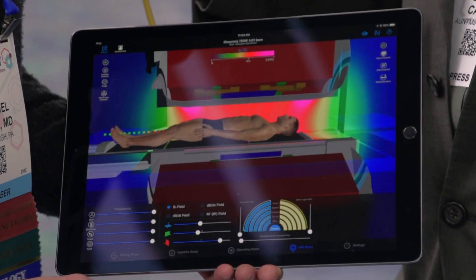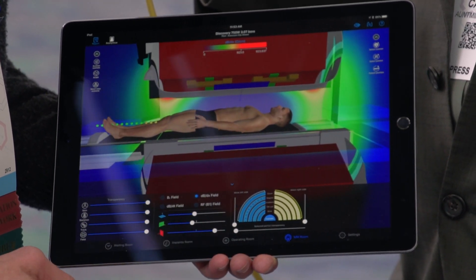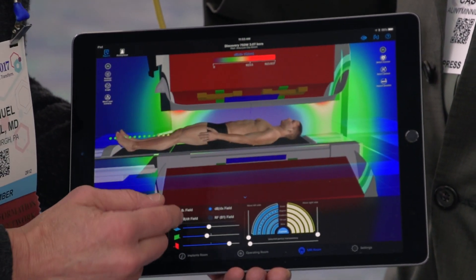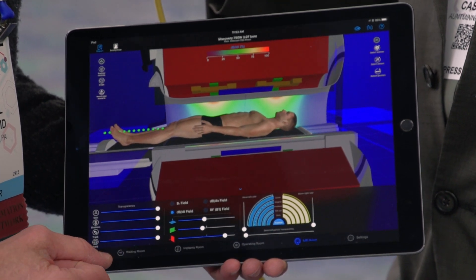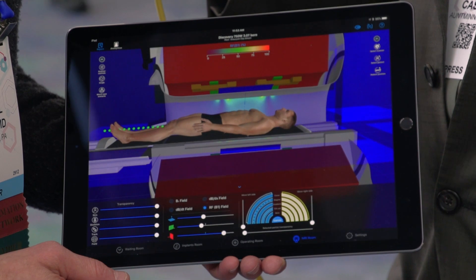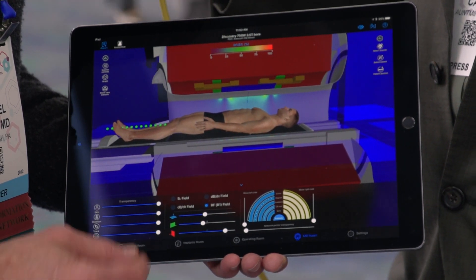Stronger where it's redder and purple, weaker as it gets to the greens and to the blues. Here is the magnetic spatial gradient, and notice it's a very different energy field, very different distribution, almost zero in the center, strongest out at the edges. Here is the imaging gradient magnetic fields, and again you can see a different distribution. Here are the radio frequency energies that are being distributed over the patient.